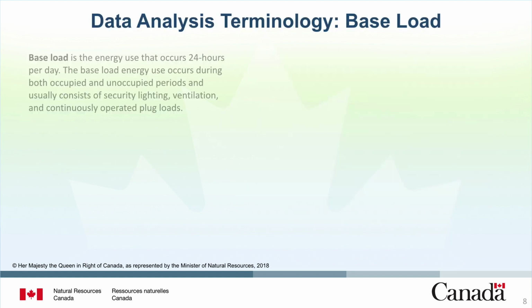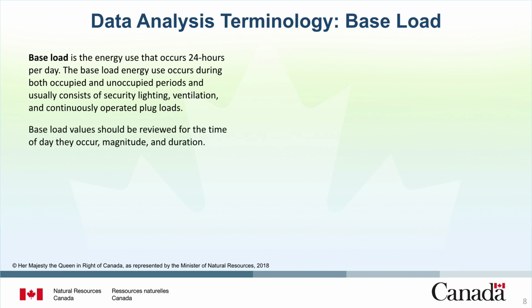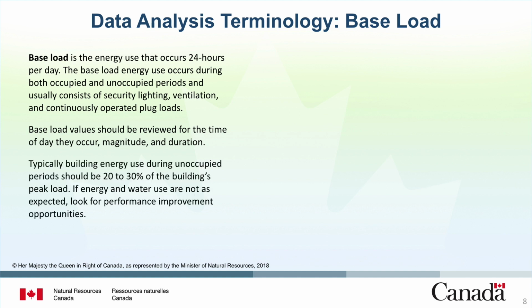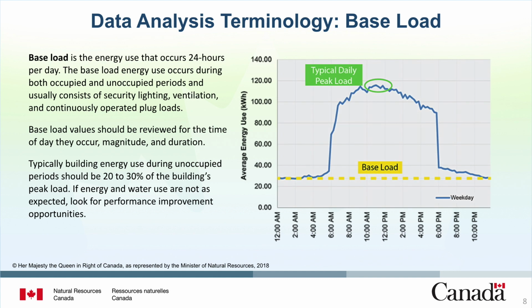Next is base load. Base load corresponds to the energy use that occurs 24 hours per day. The base load energy use occurs during both occupied and unoccupied periods, and usually consists of security lighting, ventilation, and continuously operated plug loads. Base load values should be reviewed for the time of day they occur, magnitude, and duration. Typically, building energy use during unoccupied periods should be 20 to 30% of the building's peak load. If energy and water use are not as expected, look for performance improvement opportunities. The graph provided is of a load profile with the base load identified by the yellow dotted line, illustrating the base energy use of around 25 kilowatt hours across the 24-hour period.